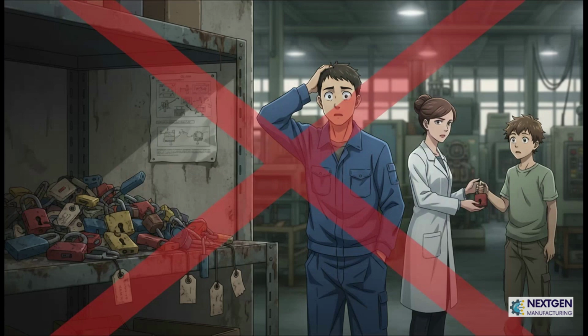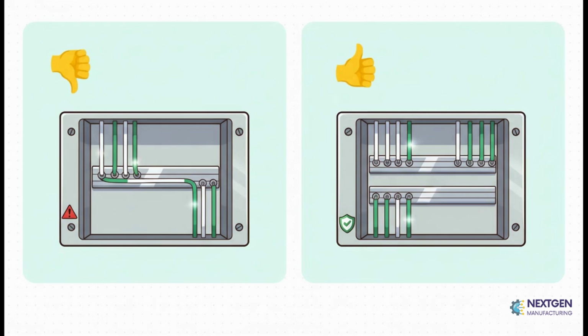All right, Pillar 3 is all about using and installing equipment correctly. Let's start with grounding. A super frequent and dangerous mistake is bonding the neutral and ground wires together in a subpanel. This should only ever happen once, right at the main service entrance. When you do it downstream, you create parallel paths for current, which can energize metal frames and enclosures that should be totally safe to touch.